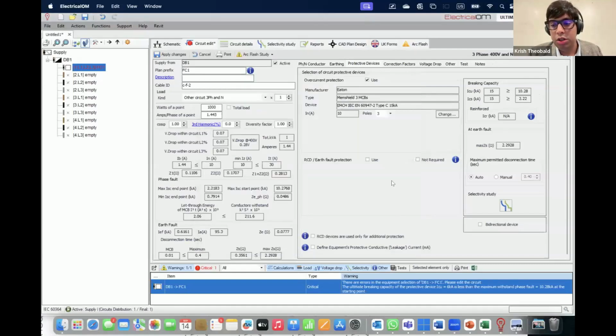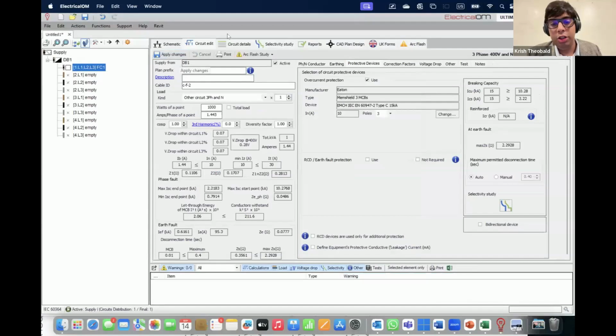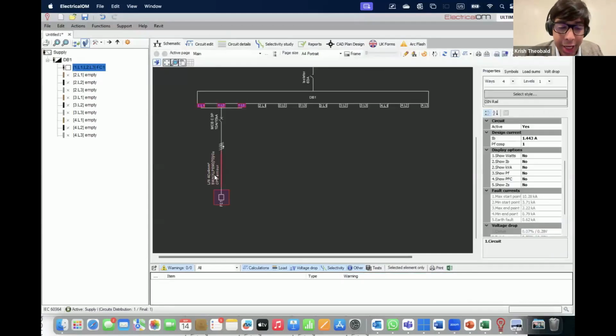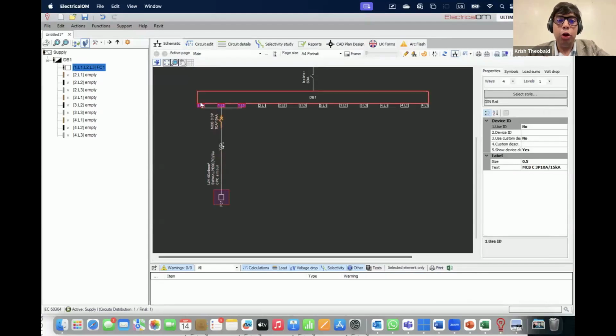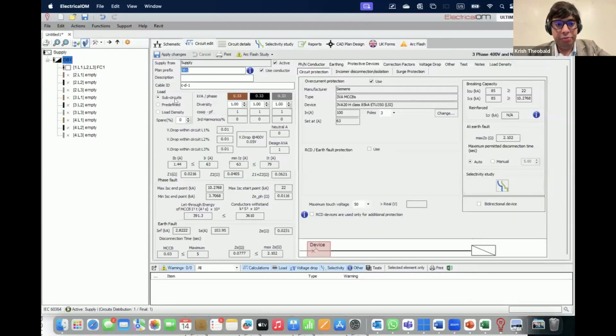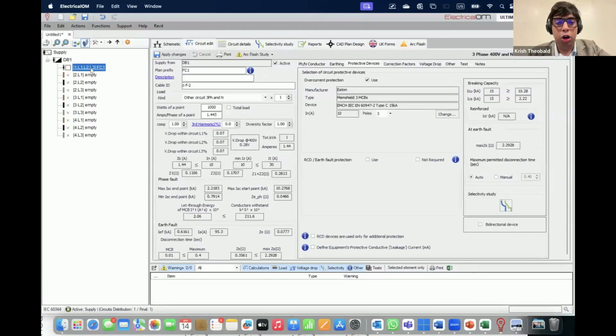If I now say take a different device, say an Eaton device, Memshield 3, say I do a 15K type C, 10 amps, and now I refresh, that fault goes away. So the software is quite intelligent in that sense. Anyway, so now we've selected the load. We need to obviously enter what we call our fault current.